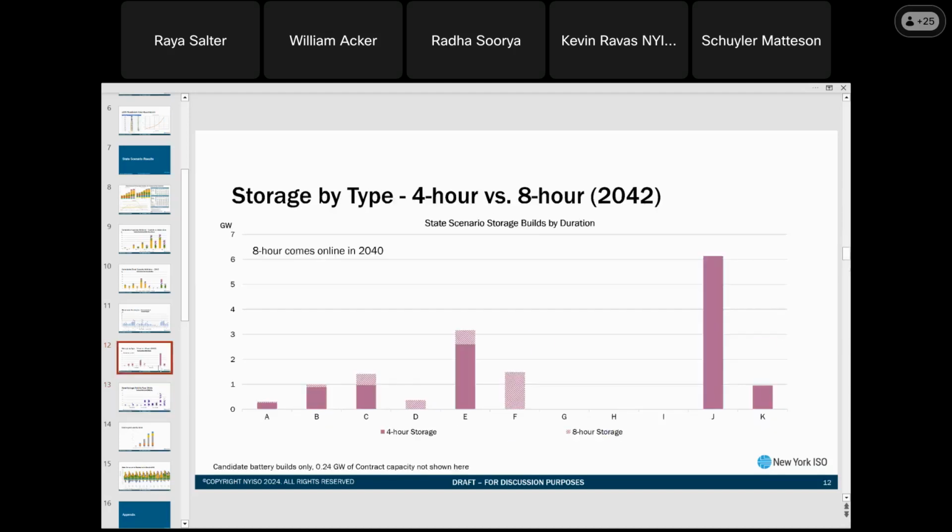And these are both still done with the 0 state of charge at the beginning of the day. So a use case for a 4-hour storage would be that solar generates a lot in the afternoon. It doesn't do anything in the morning before you have over capacity, but after the afternoon you've got a lot of solar power, and then it's discharging in the night. The 8-hour, the same scenario, 0 state of charge at the beginning of the day. I suspect that is a very weak use case for 8-hour compared to other use cases, just so we understand how it's modeled.